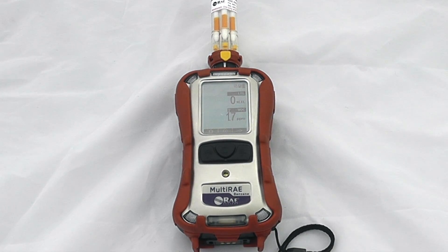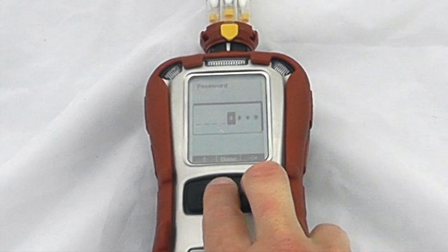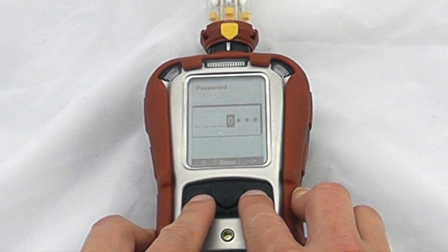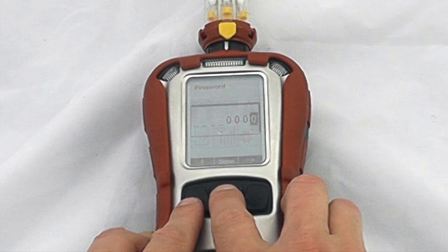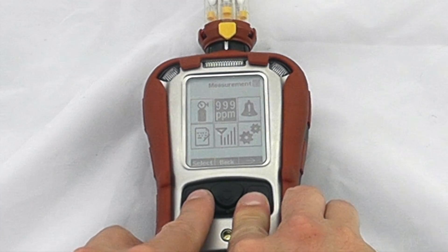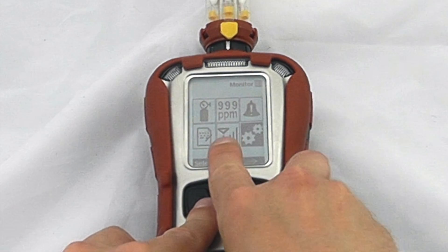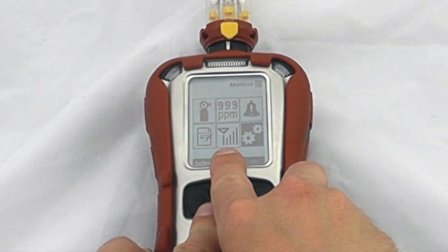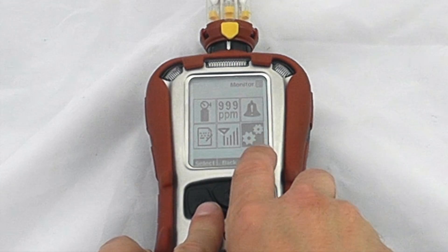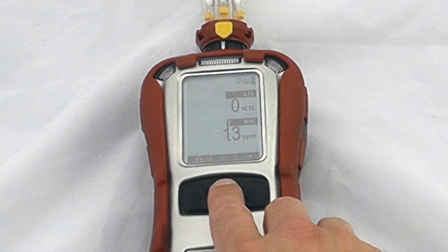Everything operationally is exactly the same as the general MultiRAE instrument — there is another video on our YouTube channel going through that specific device. To briefly cover the back menu: holding the mode and no buttons simultaneously will ask for a password — the default is 0000 — and now we're in the back menu. We've got calibration span, zero settings, measurement settings such as correction factors, alarm settings, data log settings, and if you had a wireless-enabled unit, wireless options to talk to the EchoView or similar. To go back, return to general measurement mode.